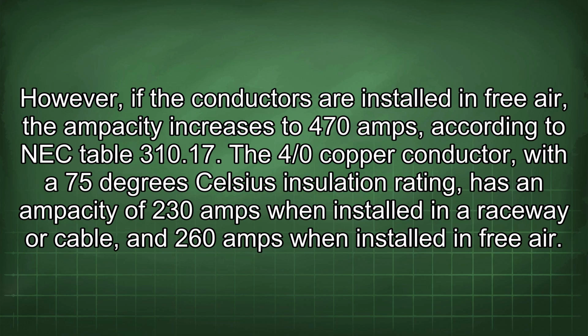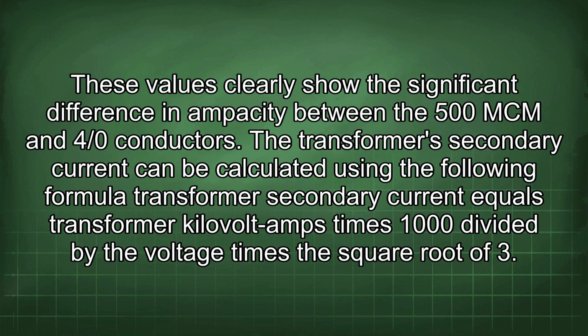The 4/0 copper conductor, with a 75 degrees Celsius insulation rating, has an ampacity of 230 amps when installed in a raceway or cable, and 260 amps when installed in free air. These values clearly show the significant difference in ampacity between the 500 MCM and 4/0 conductors.